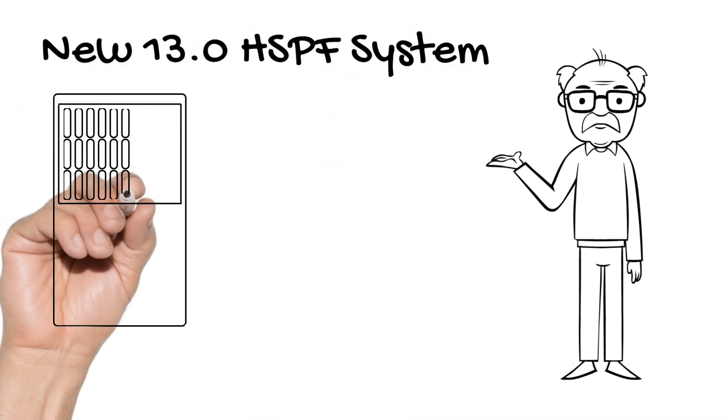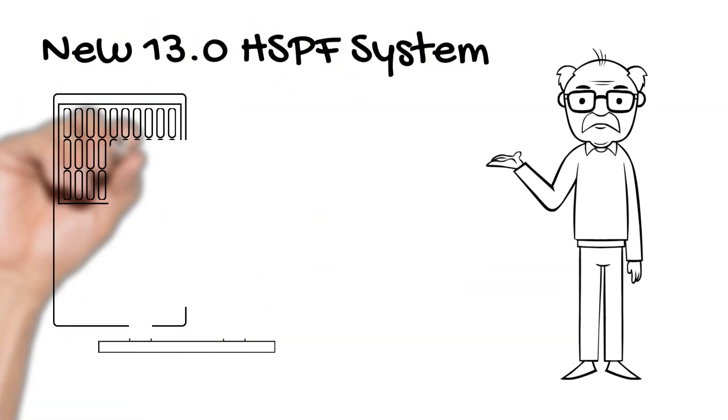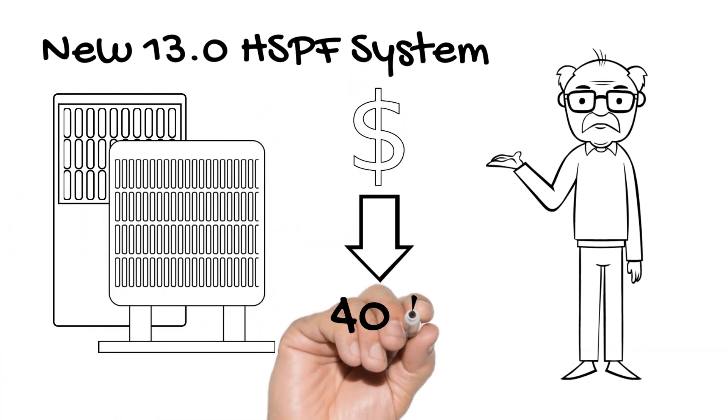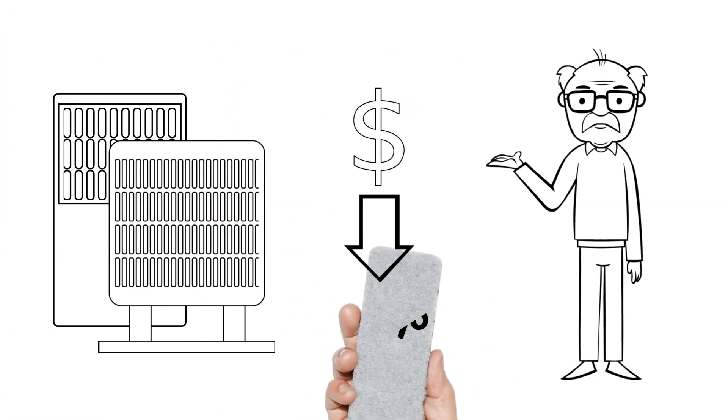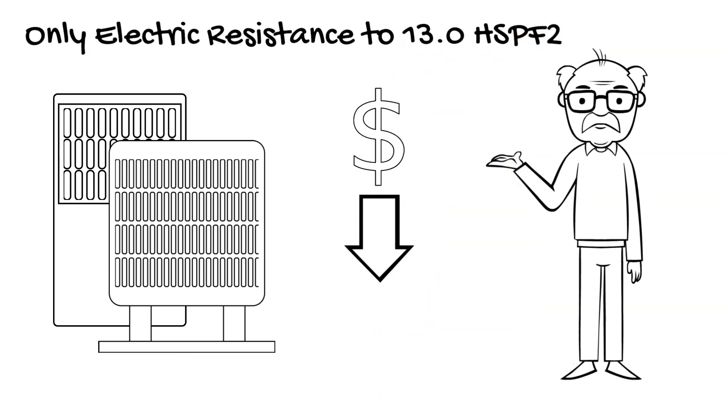It is not uncommon for some older heat pump systems to have an HSPF of 6.0 or even lower. If that is your situation, a new 13 HSPF2 system would reduce your heating cost by over 40%. If you are using only electric resistance heating, a 13.0 HSPF2 would reduce your heating bill by a whopping 70%.